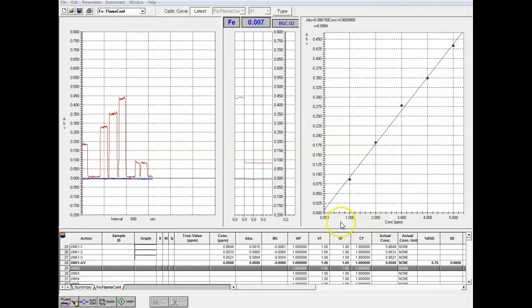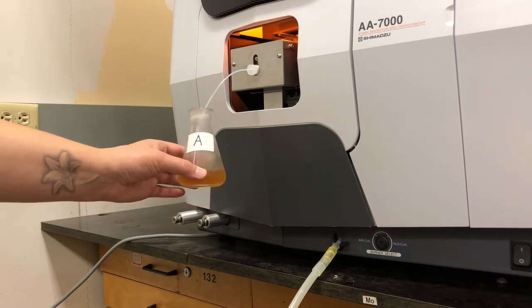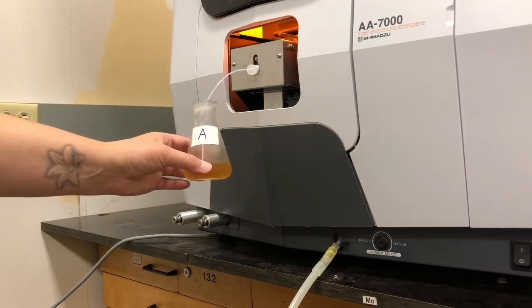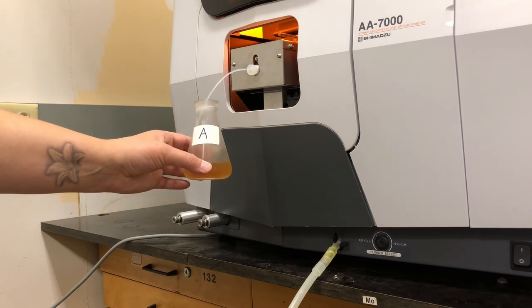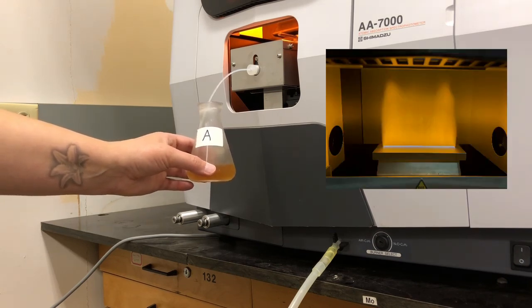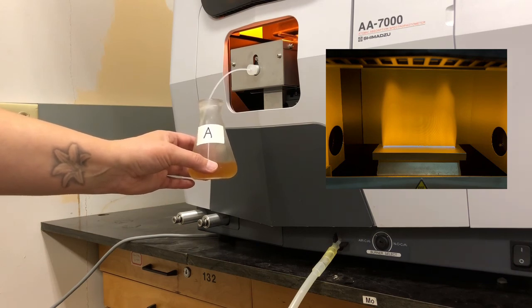Our standards are all done, and you can see our calibration curve is now complete with our 5 points. We look at our R² value, 0.9984, that's not bad. So we have a pretty good standard calibration curve that we can use for determining the results of our unknown samples. Now when we do our sample, we put it on the machine the same way we did with the standards. We have the solution that we made up earlier. We just put it under the surface of the water, exactly the same thing that we did with our standards. You can see the difference in the color of the flame there. Then again, we just hit start on our software.